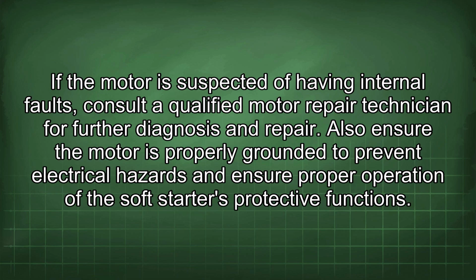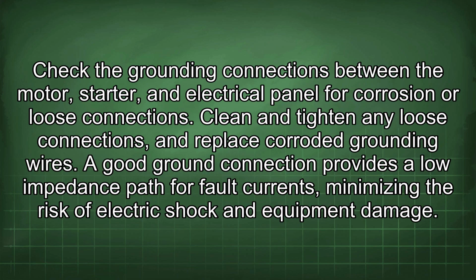Also ensure the motor is properly grounded to prevent electrical hazards and ensure proper operation of the soft starter's protective functions. Check the grounding connections between the motor, starter, and electrical panel for corrosion or loose connections. Clean and tighten any loose connections and replace corroded grounding wires. A good ground connection provides a low impedance path for fault currents, minimizing the risk of electric shock and equipment damage.